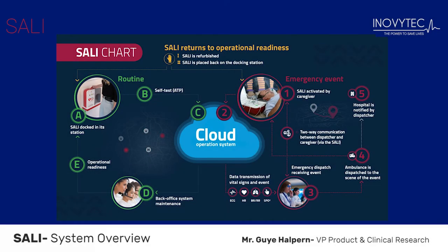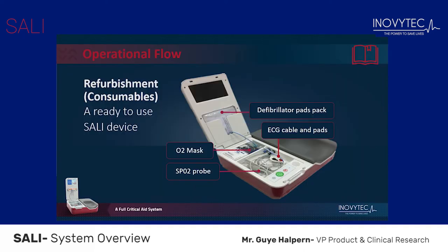The following chart is a summary of the system's operational flow. SALI has a secure cloud-based system that manages its communication and data transmission. During routine time, SALI is docked on its docking station; every 12 to 24 hours, a routine automated test protocol is sent, verifying that the SALI is ready to use. During an emergency, once used, the patient's parameters are sent to the emergency dispatch, allowing the dispatcher to evaluate the situation and decide which ambulance to send. Once the event is over, the SALI is refurbished and placed back on its docking station.